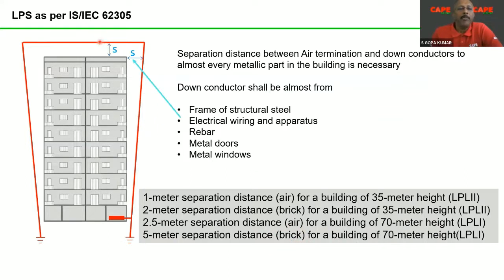Insulating material is nothing but, between the air terminal and the down conductor, you have to put some support. And if that support is brick, or if the distance which we are calculating from the air terminal to the metallic part is physically separated by brick, you need almost 5 meters for a 70 meter building with this lightning protection level. This means the air termination system in the last case has to be 5 meters away from your RCC building. Just imagine, is this practically possible? Practically, keeping the air termination or down conductor away from the building is very difficult. You would need to make a 5 meter FRP support, and you have to make the mesh 5 meter above the building, on the side 5 meter away from the building, which is practically impossible.